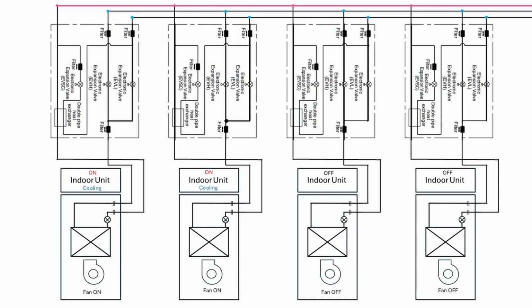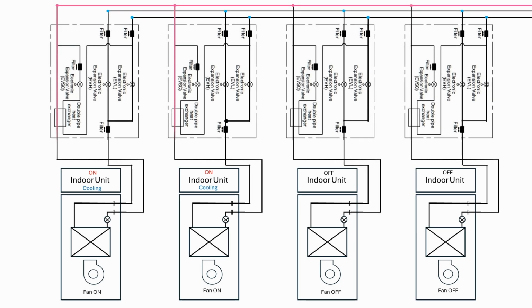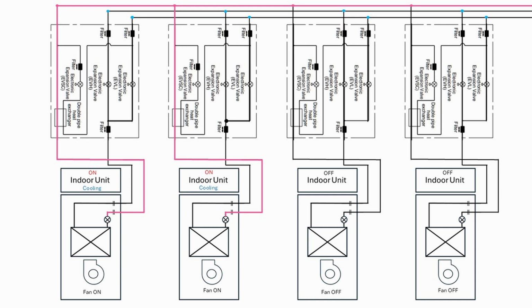The branch selector is available in either a single version, with 1 indoor unit connected to 1 branch selector box, or a multi version, with up to 12 indoor units connected to 1 branch selector. In this example, there is an individual branch selector box for each indoor unit. The liquid refrigerant travels through the branch selector box to the indoor units that are calling for cooling. As the liquid refrigerant enters the indoor coil, it travels through an electronic expansion valve which meters the refrigerant.